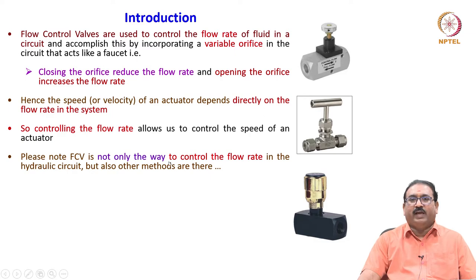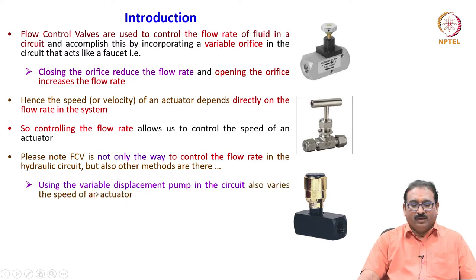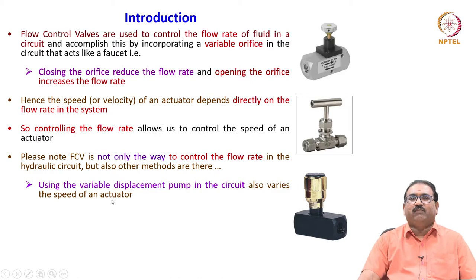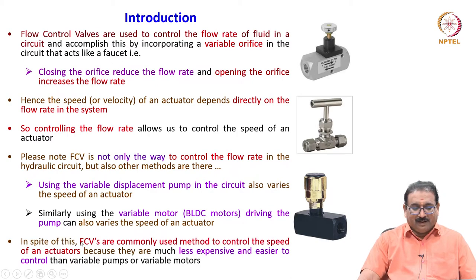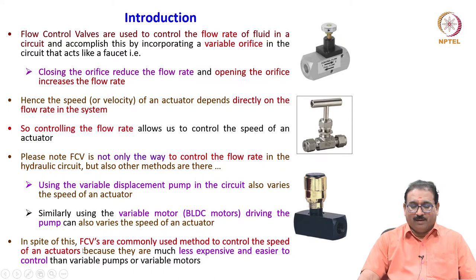Please note, an FCV is not the only way to control the flow rate in a hydraulic or pneumatic circuit — other methods exist. Some of them include using a variable displacement pump in the circuit, which varies the speed of an actuator by varying the flow rate. Similarly, using a variable motor, like a BLDC motor driving the pump, can also vary the speed of an actuator. In spite of this, FCVs are the commonly used method because they are much less expensive and easier to control than variable pumps or variable motors.